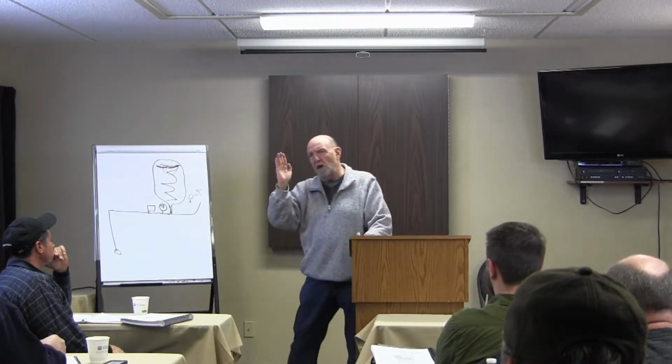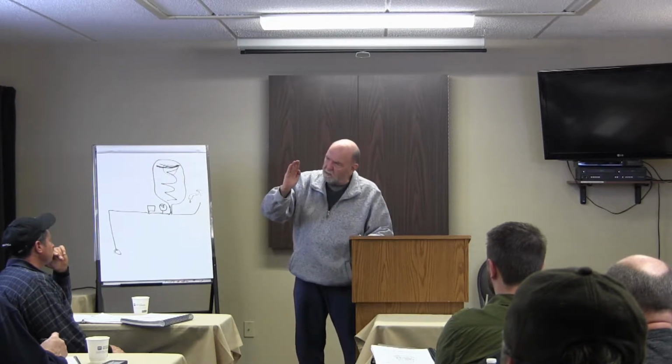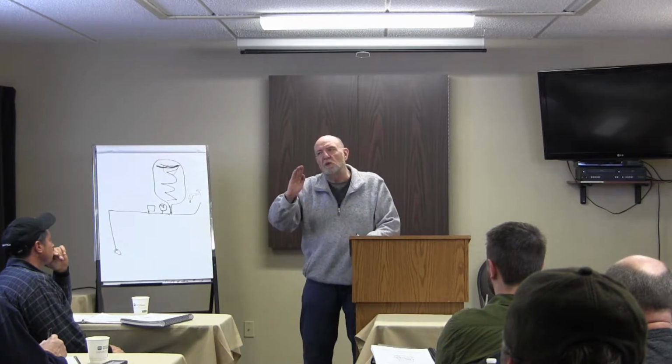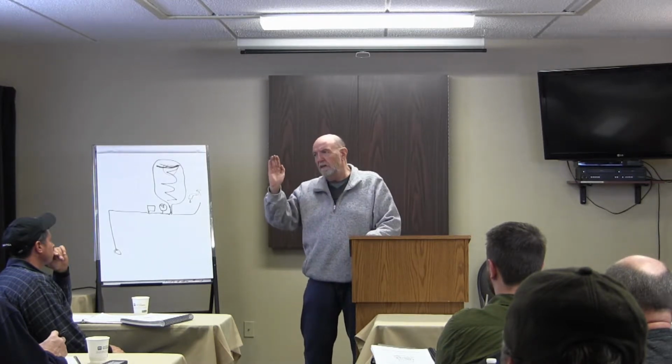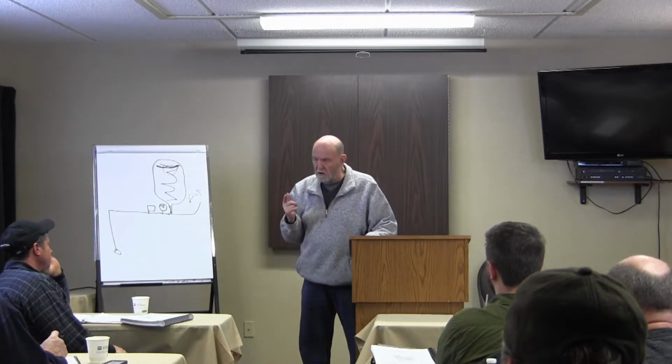But on a system operating properly, it'll hit 40, and then you'll hear a click, and it starts working its way down. About a minute later, it'll hit 20, and then you'll hear a click, and it starts working its way back up. It's working properly. If it's anything else other than about a minute, then it's cause for concern.